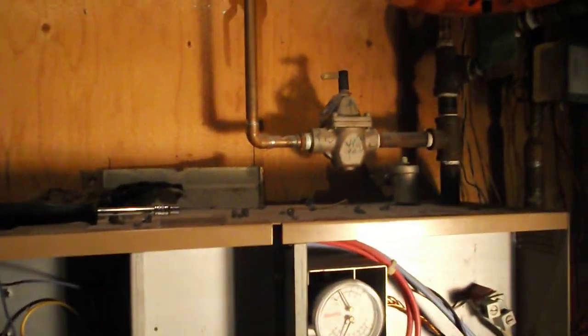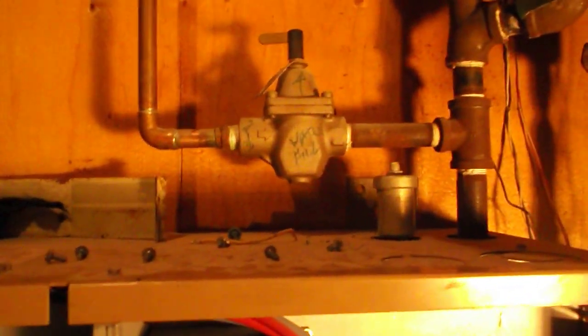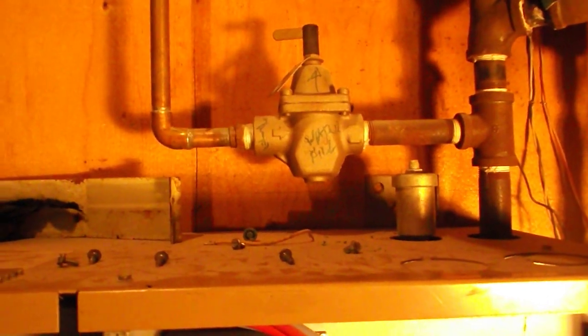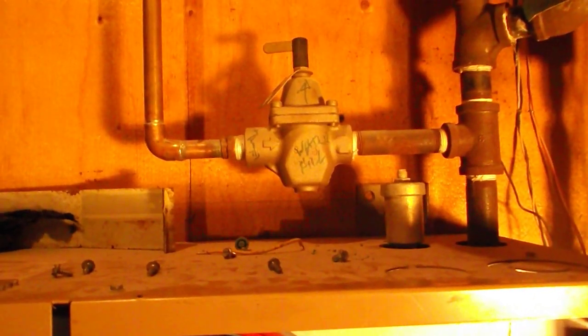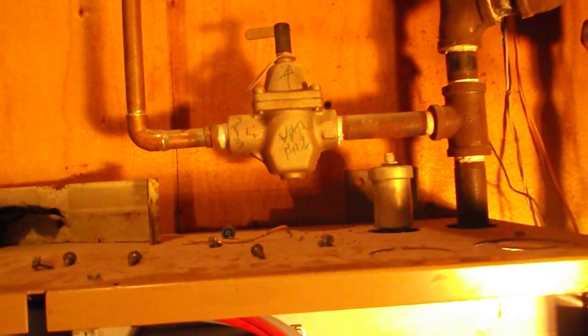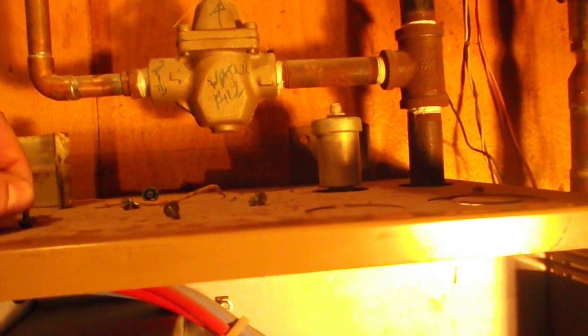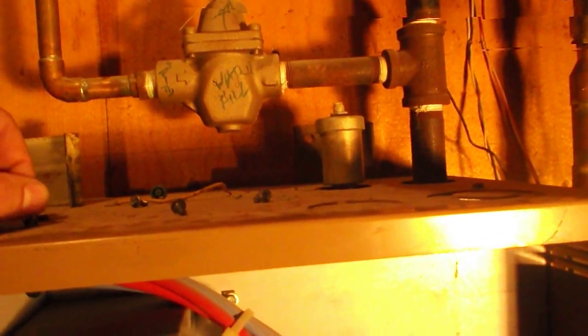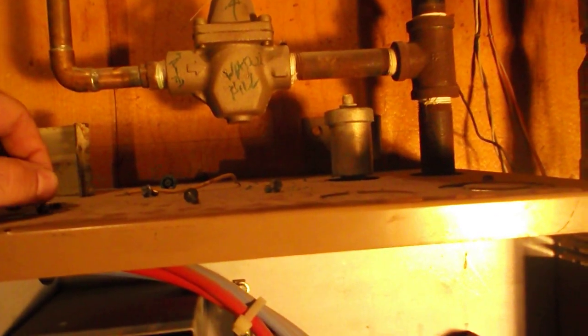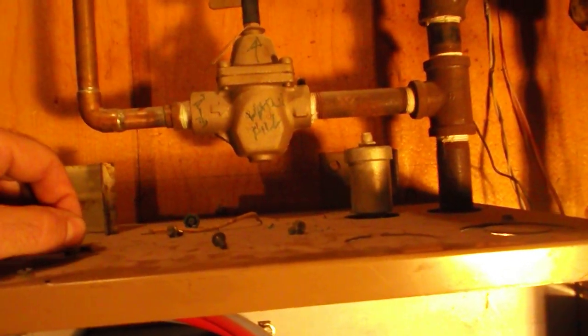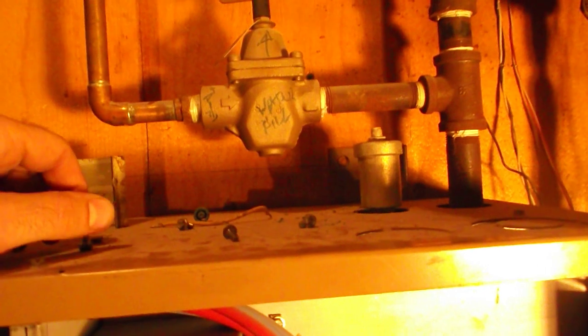One other comment while we're here is when we started troubleshooting a couple of days ago, the water pressure in the unit was zero. And obviously that was due to a leak, and we now know the source of that leak. It's the actual boiler itself. So over the last 5 or 6 months without use, it leaked out through that very small hole.